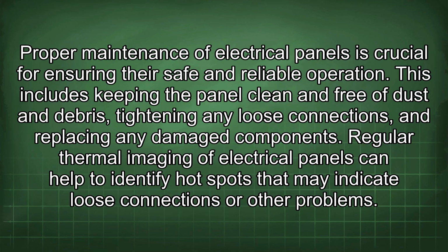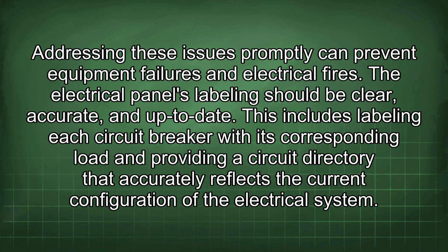Proper maintenance of electrical panels is crucial for ensuring their safe and reliable operation. This includes keeping the panel clean and free of dust and debris, tightening any loose connections, and replacing any damaged components. Regular thermal imaging of electrical panels can help to identify hot spots that may indicate loose connections or other problems. Addressing these issues promptly can prevent equipment failures and electrical fires.